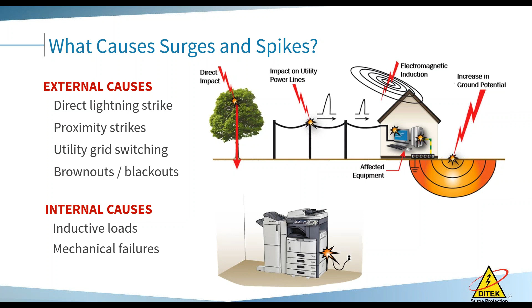Internal causes come from inside the building. We show a picture of a copier here, but it's not just the copier, it can be HVAC, motors, drives, and similar equipment. I live in Florida, and as a small example, I know before my AC kicks on because my lights dim just a little bit. As these things get up to speed and turn off, they dissipate excess current and voltage around the property. The bigger the chiller on the roof or side of the building, the bigger the transient when it shuts off. Copiers are notorious for this too. A lot of times people think a finished office environment doesn't have to worry about surges, but they're created inside the building the majority of the time. Some say three-quarters of the time or more, surges are internal.